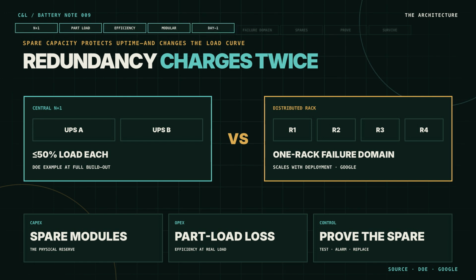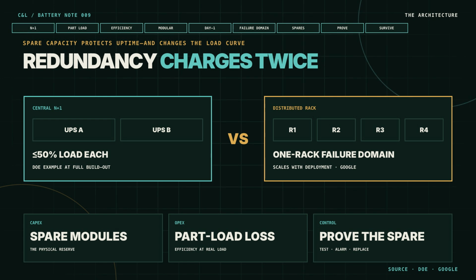Modular design changes that trade-off. Smaller units can be added as the data hall fills, keeping utilization higher and delaying some day-one spending. Google makes the same architectural point from the rack side. Its distributed battery backup scales with deployment, reduces the failure domain to one rack, and removes intermediate conversion steps between the battery and the machine. None of that makes redundancy free. It changes where the spare capacity sits, how fast it can be replaced, and how many failure domains one event can reach. The hidden bill is therefore architectural. Buyers pay for spare modules, spare paths, and enough operational discipline to prove those spares will work when the active path does not.